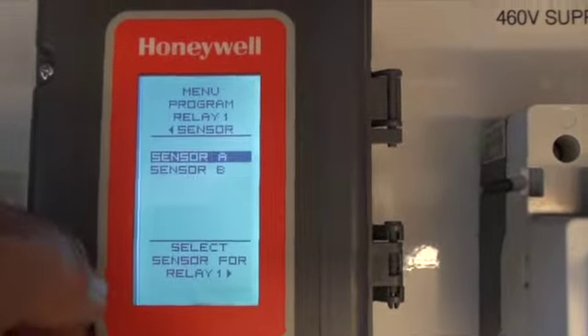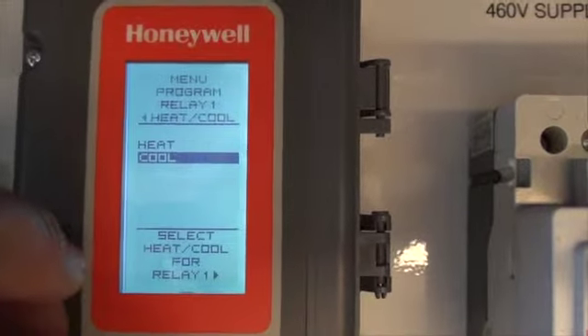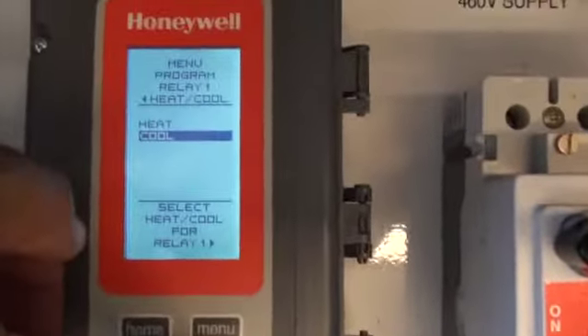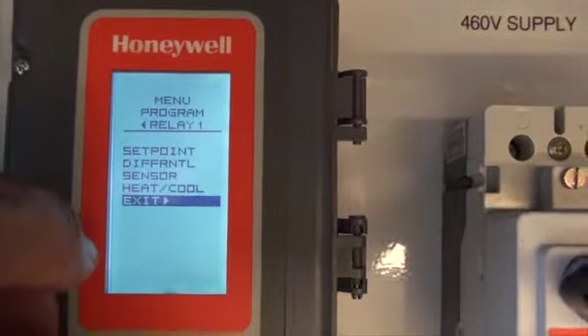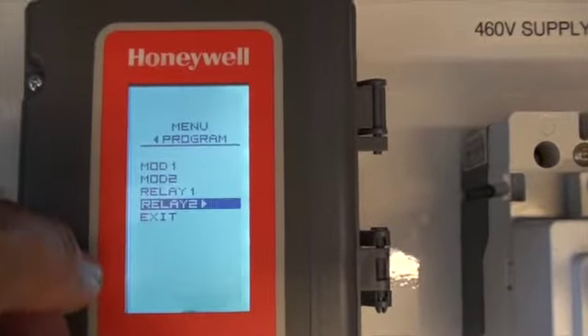I don't need to worry about the sensor. Press that twice. It's set up in the cooling mode. Again, up and down arrows move and once you press the right arrow key, it locks it in. Press the exit key, it goes down to relay 2.